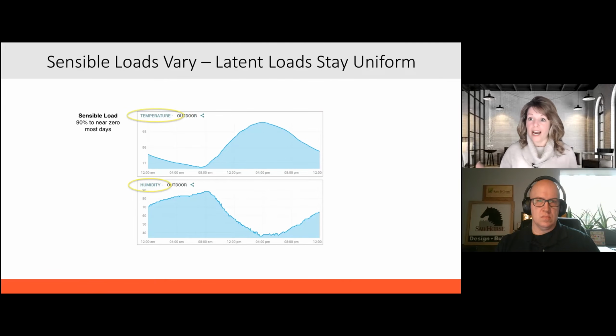And also with that, we now understand that the relative humidity is associated with the temperature. So in the mornings, here we've got the humidity. Our RH is high, our temperatures are low, and as the day heats up, our RH goes down. So you think you understand the whole picture here, but the reality is the dew points are the same. The same amount of water that was in the air in the morning is the same amount of water that's in the air outside in the afternoon. So we really need to understand dew point, because that tells us what the absolute water is in the air. So latent load is fairly uniform throughout day and night. So again, we need to understand dew points to really understand how much moisture is in the air.